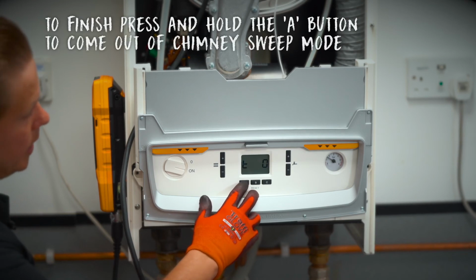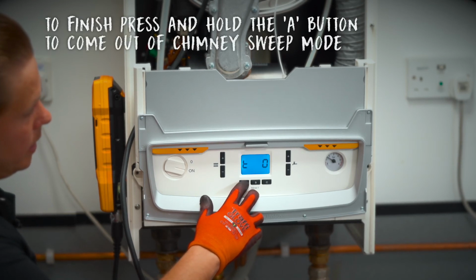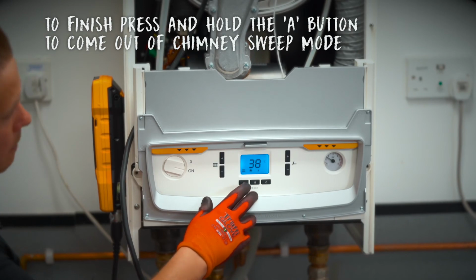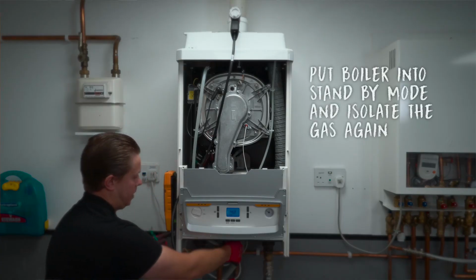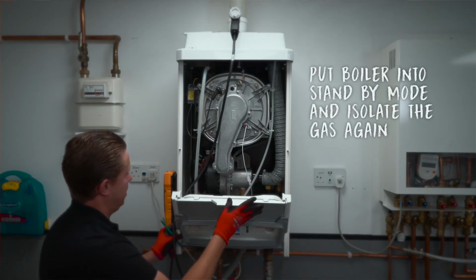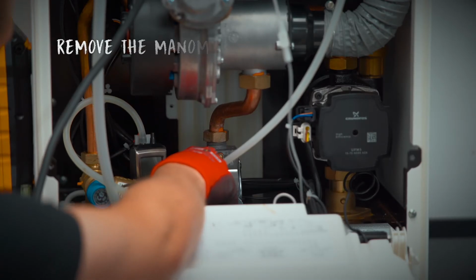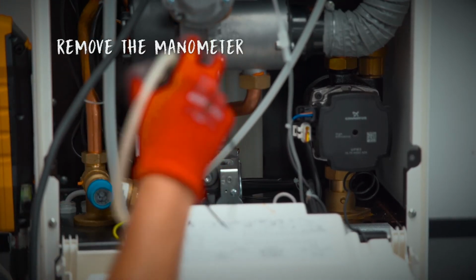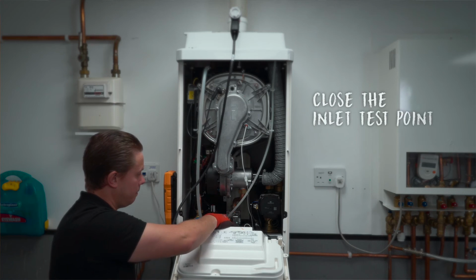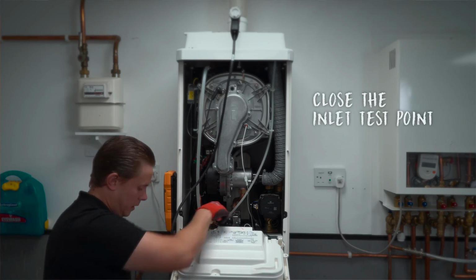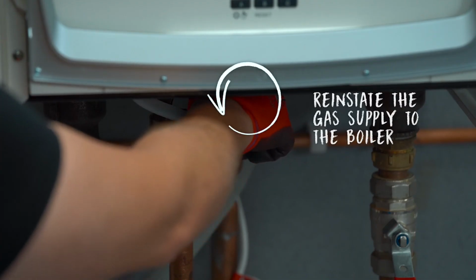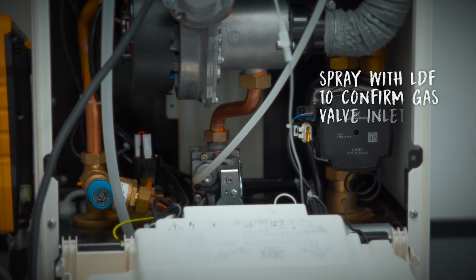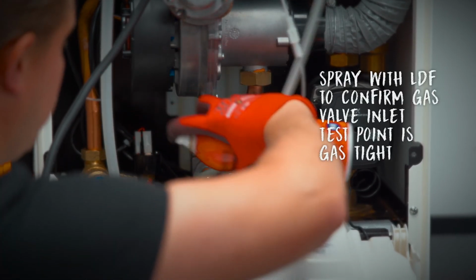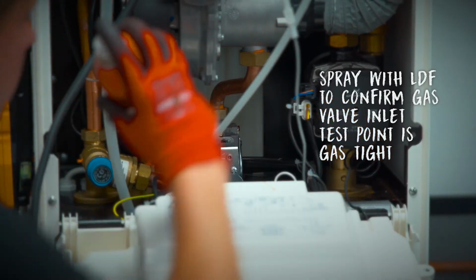To finish, press and hold the A button to come out of chimney sweep mode. Then put the boiler into standby and isolate the gas again. Remove the manometer and close the gas inlet test point before reinstating the gas supply to the boiler. Use LDF to confirm the gas valve inlet test point is gas tight.